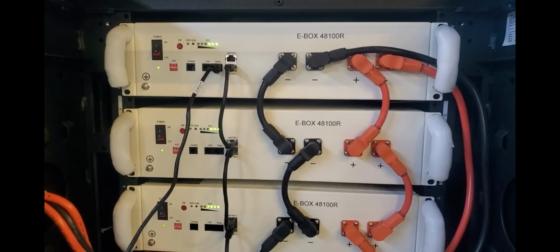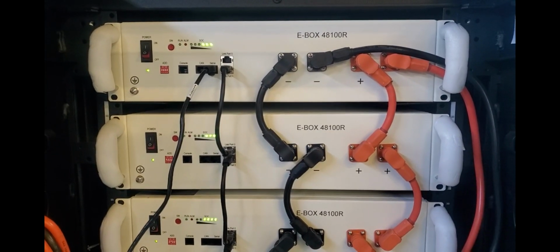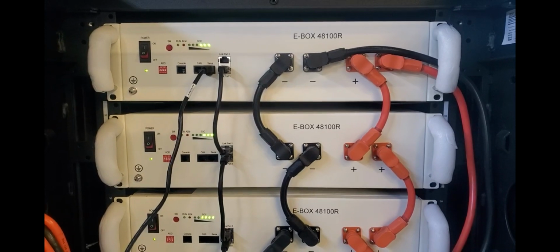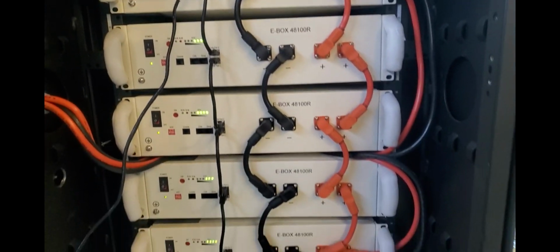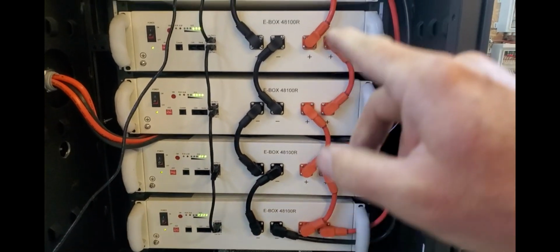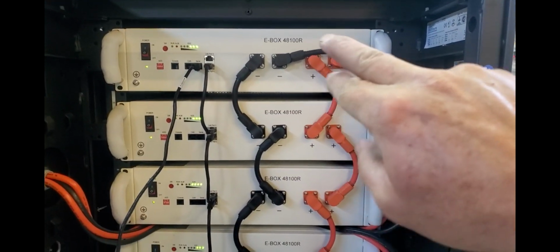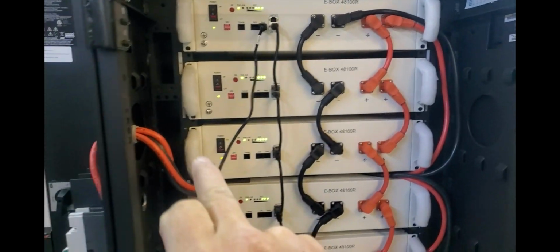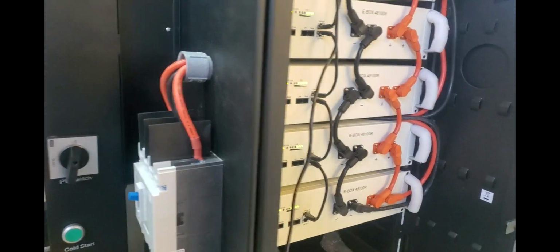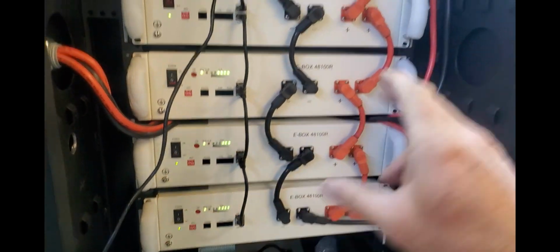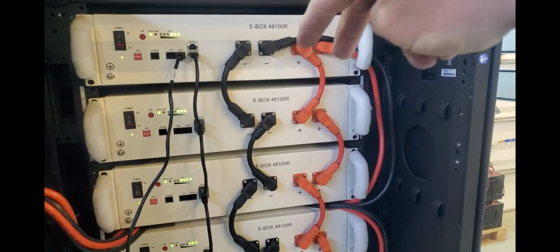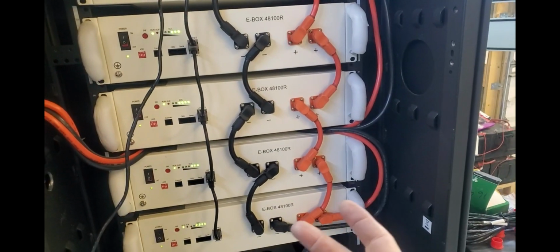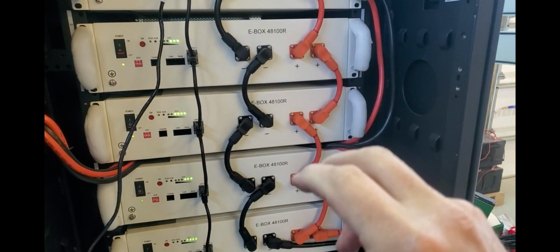So these are the Pytes, 100 amp hour, 48 volts, 5.1 kilowatt hours each. I have five of them over here hooked up in parallel, and you can see I've got two wires coming out the top going into the breaker over here, and another two wires out the bottom going in. So I'm actually paralleling, feeding in from the top and from the bottom and drawing from the top and the bottom to kind of balance the array.